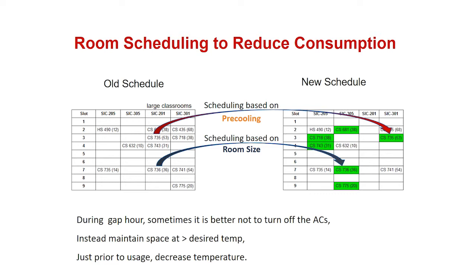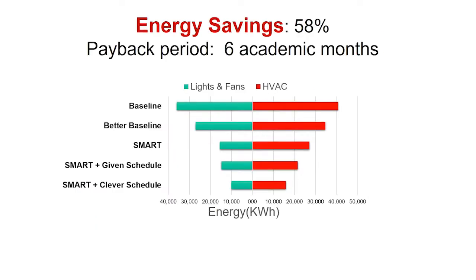And we also take into account something called a gap hour. So that rather than turning off all the ACs, we maintain the temperature slightly higher than desired. And when the usage happens, just prior to that, we decrease the temperature. So that way you capitalize on the pre-cooled area, but not consume all the energy required to maintain at that temperature.